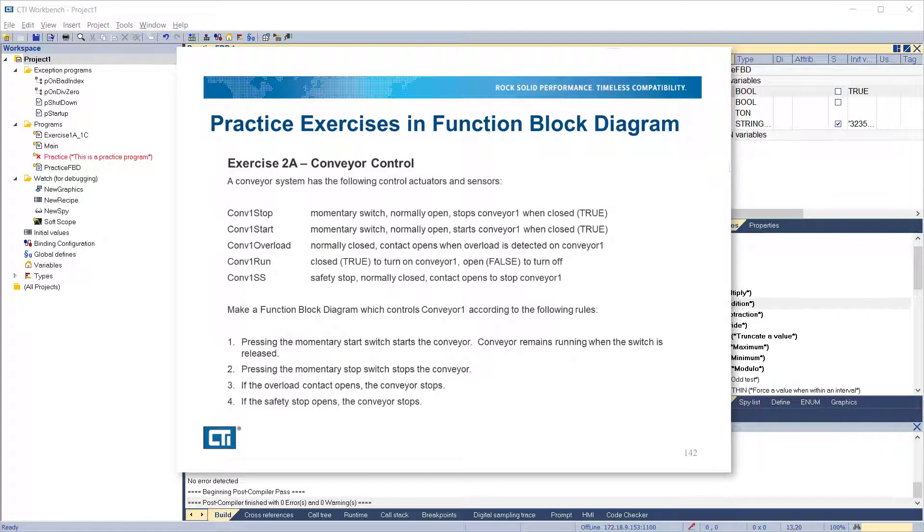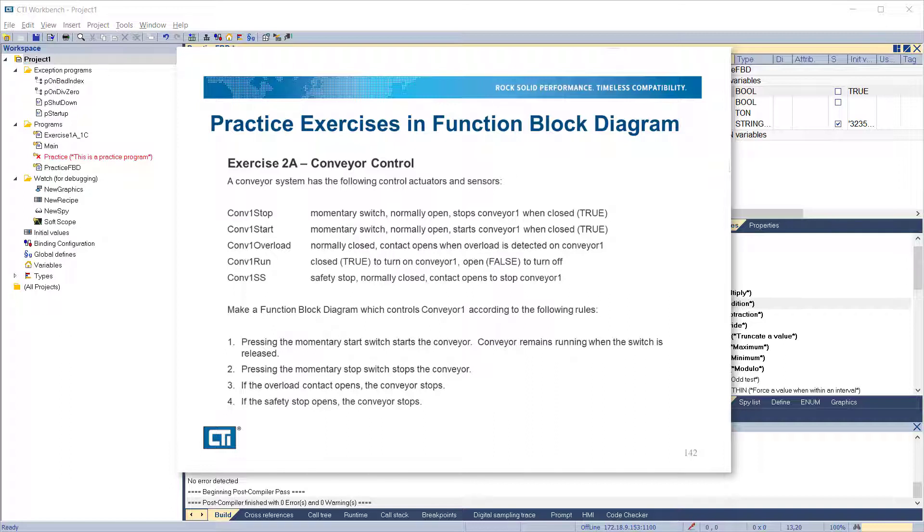In exercise 2a, we'll write a program in function block diagram to control a conveyor. The conveyor system has the following control actuators and sensors: Conveyor 1 stop is a momentary switch, normally open, which stops conveyor 1 when closed. Conveyor 1 start is a momentary switch, normally open, which starts conveyor 1 when closed. Conveyor 1 overload is a normally closed contact, which opens when conveyor 1 overload is detected on conveyor 1. Conveyor 1 run, close to run conveyor 1, open to stop.